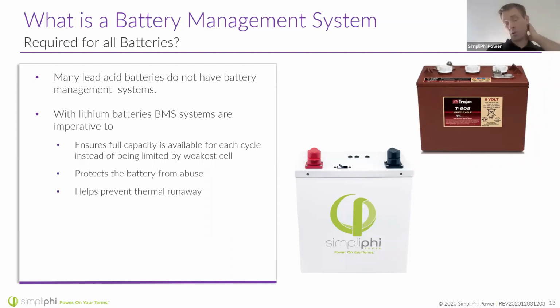There are installation costs to take into consideration as well, and lead acid batteries are really not the way to go anymore. Lithium batteries have gotten better and better, and the BMS units inside them ensure we can use the full capacity of the battery. That's done by balancing, which we'll talk about. It protects the battery from abuse and helps prevent thermal runaway, which is when a battery gets overheated for any reason, maybe an external fire, or maybe the system is inside a vehicle that has a crash. Thermal runaway can result in rapid production of heat, which can cause the cells to off-gas. So it can occur, but a BMS can help prevent that.